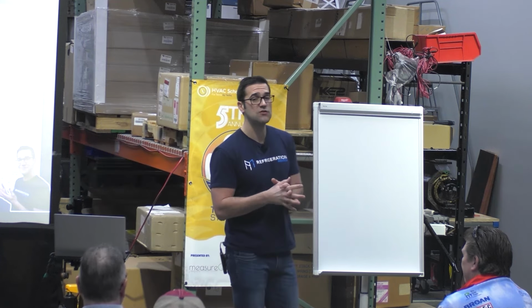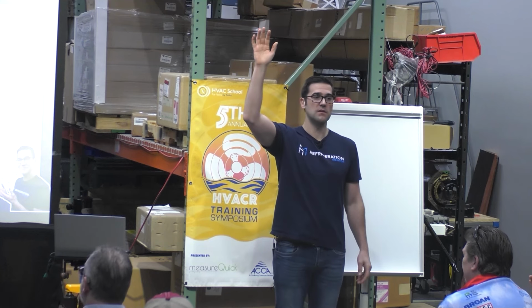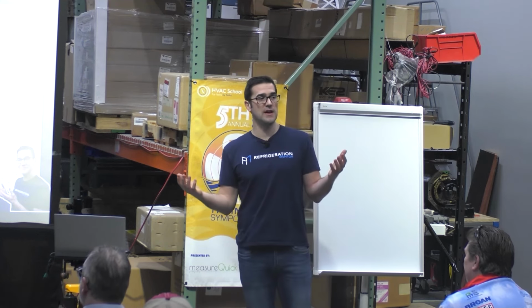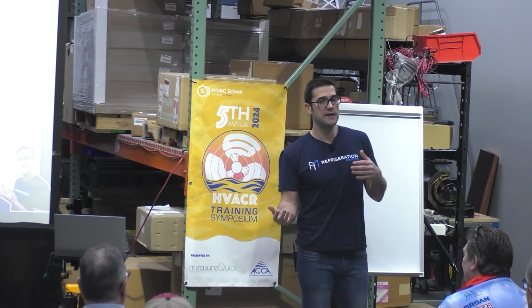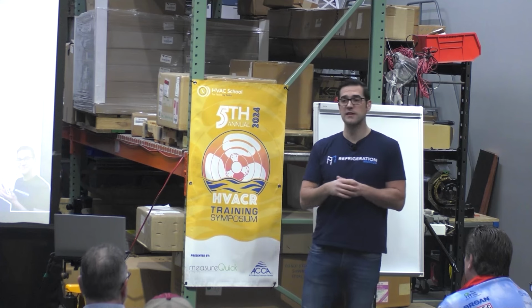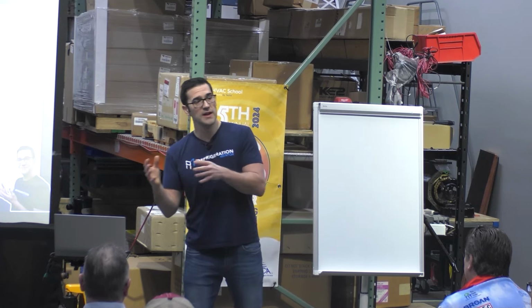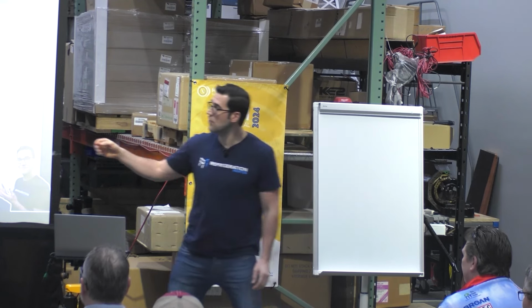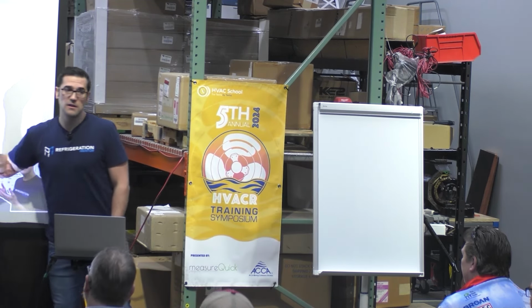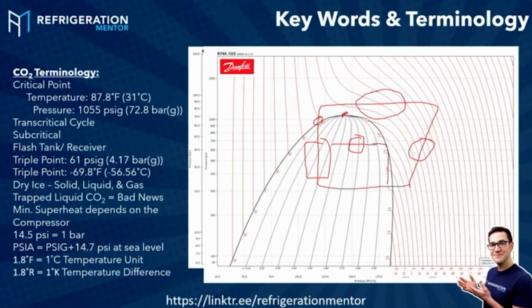How many of you have worked with electronic valves before? Show hands. We got almost everybody in here. So it's just an electronic valve. We don't want to make it harder than it is. CO2 is not as difficult as people make it out to be because they don't break it down. All these electronic valves, one here and one here, they're just opening and closing to maintain a certain set point that we as a technician set up. We're trying to maintain a certain temperature in this receiver, so that liquid is a certain temperature to go out to my metering devices.